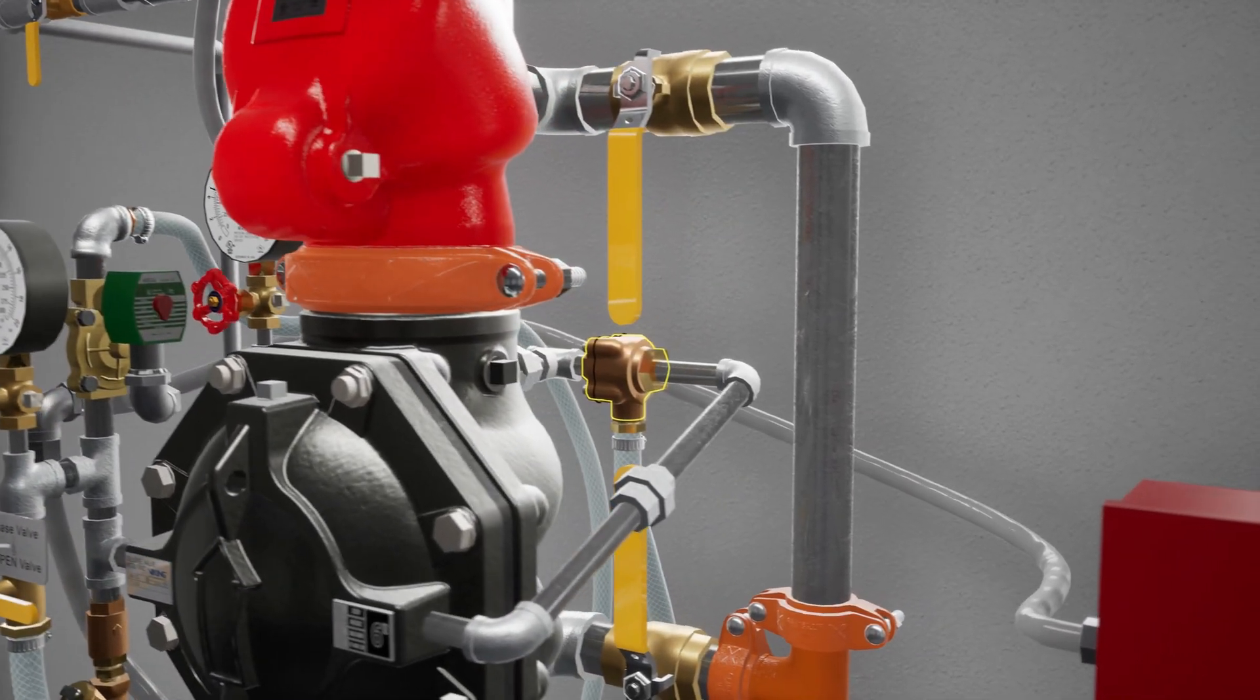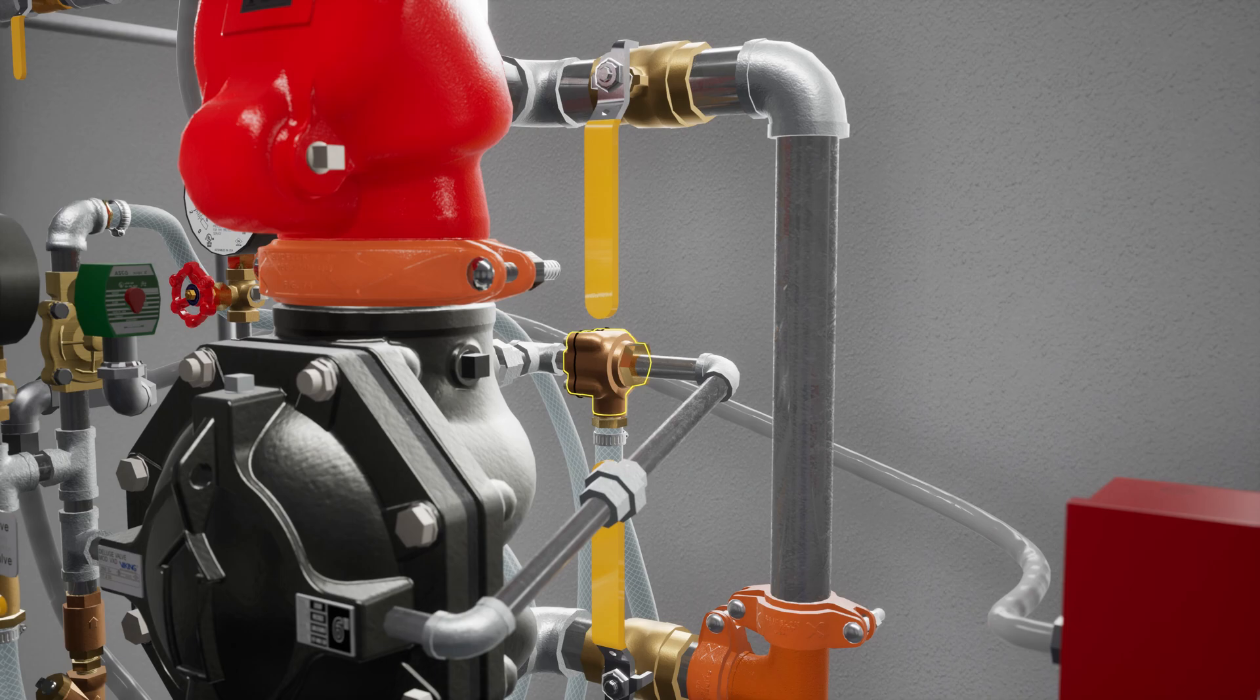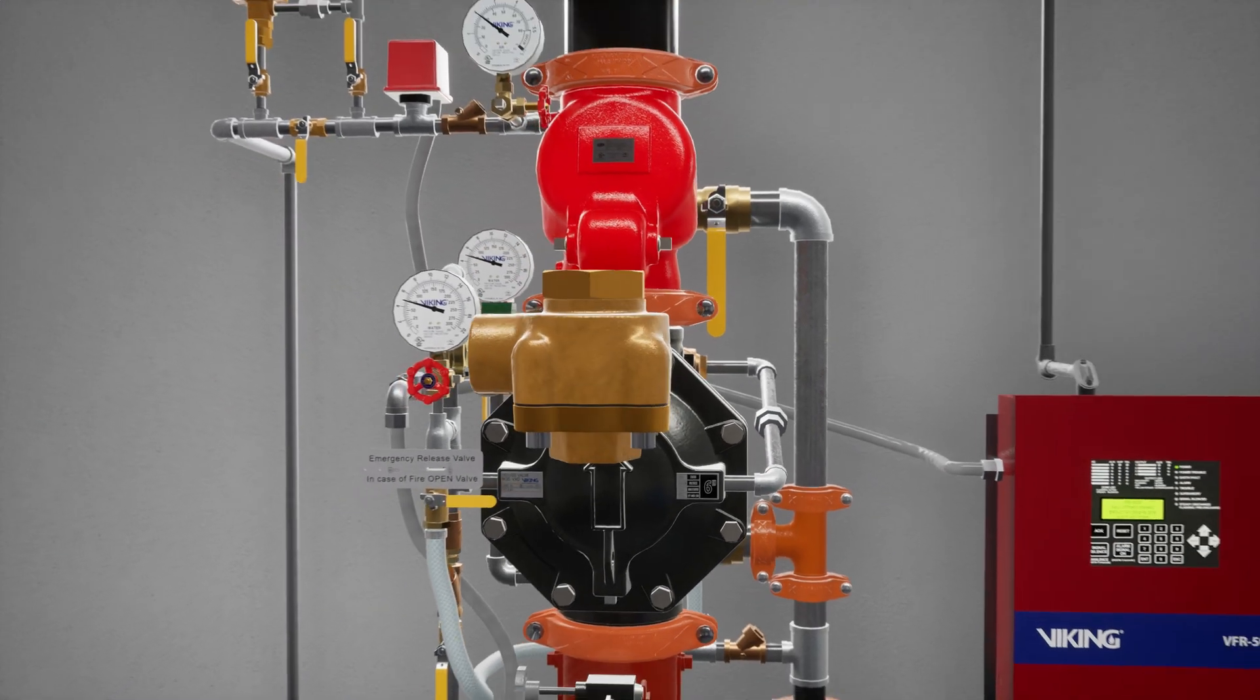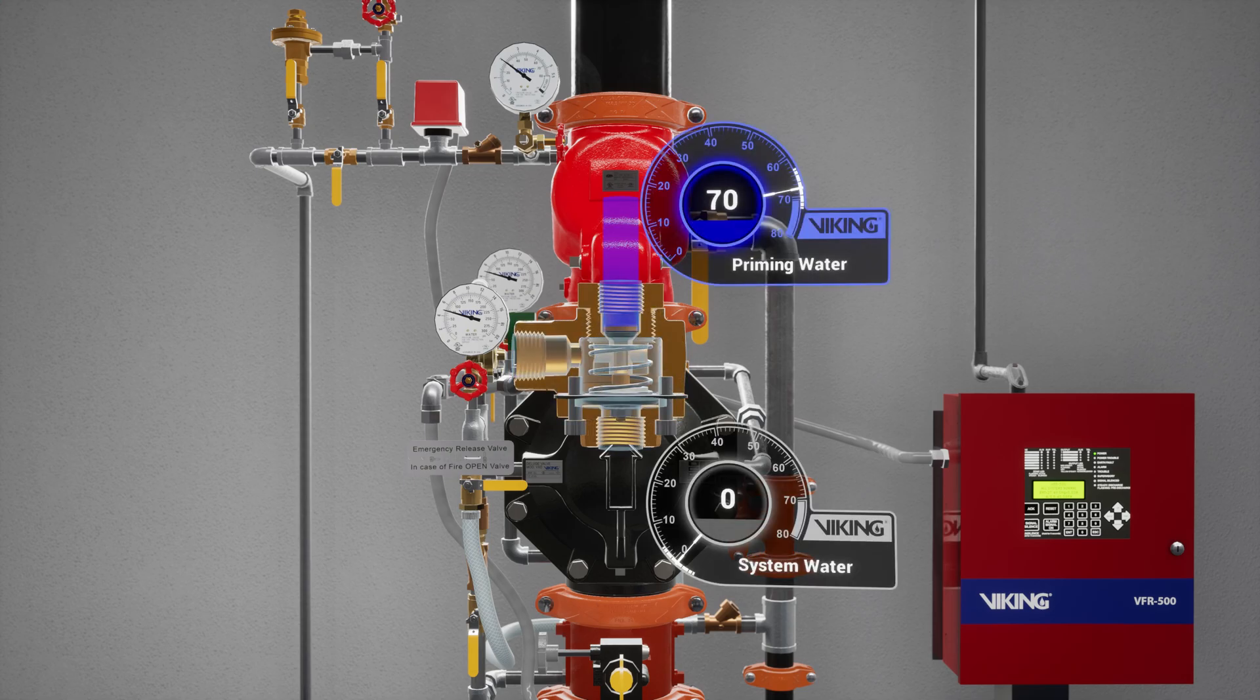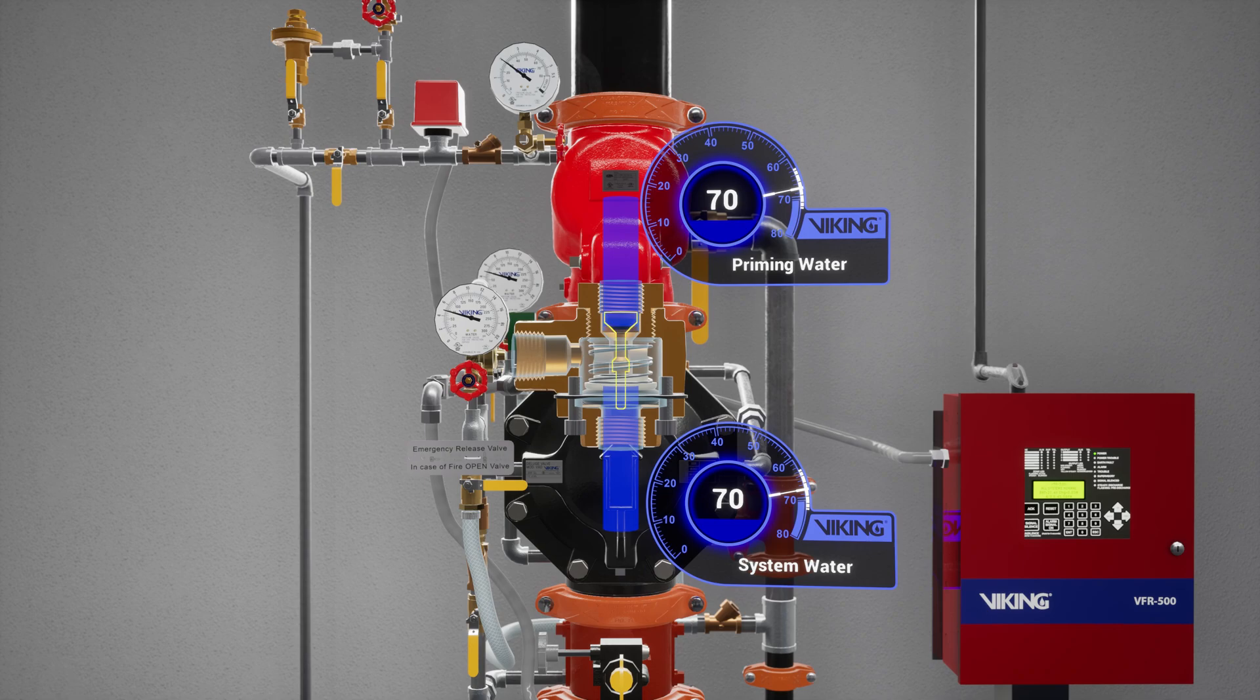Following the trim off the prime chamber is the pressure operated relief valve or PORV. The PORV is a device that ensures the valve remains in an open state while water is flowing through the valve. When water is directed to the sensing side of the PORV, the push rod is forced open. Priming water is then directed to the open drain, preventing the priming chamber from repressurizing.